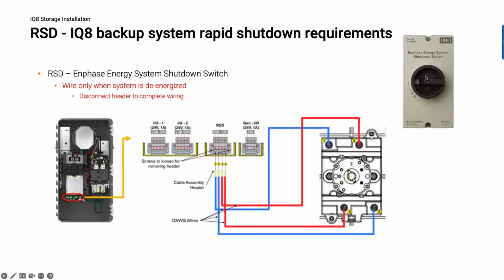The purpose of this switch, this isn't just a switch that disconnects DC power or AC power. What this switch does is it actually is a signaling device to the system controller, and the system controller does a bunch of magic to signal the inverters to stop producing power or reduce power to a safe state. So you have to use this system shutdown switch. You cannot avoid it if you're doing any kind of backup configuration.